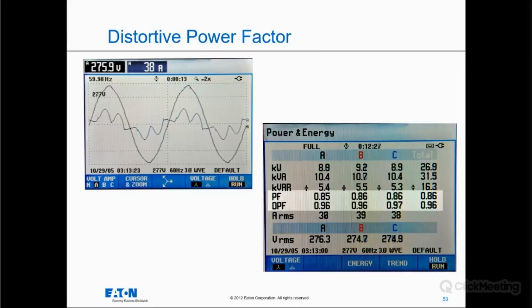Let me highlight the bars here. But if somebody just looked at the true power factor, they would say, hey, we've got poor power factor. But what is the solution here? Can you determine anything from seeing these two values? Yes, you can determine something. That is that adding capacitors is not the solution here, because you don't have just poor displacement. You have poor power factor from actually distortion. So what this is telling you is that you have a harmonics problem in this building, and adding capacitors is not going to solve that. You need to be adding harmonic correction equipment in here to correct that poor overall power factor, because the displacement power factor is not bad at all.